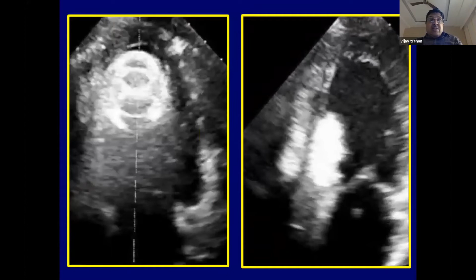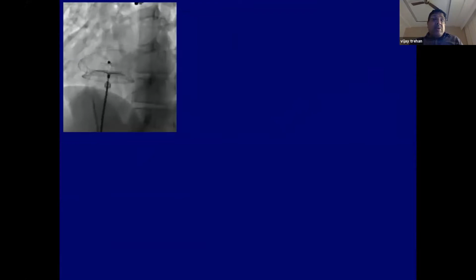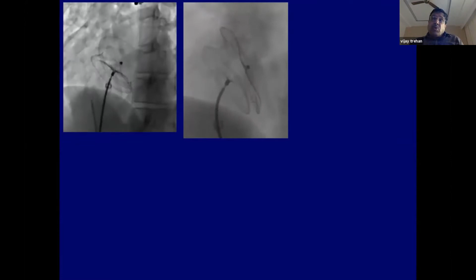So nobody will like things like this after you have delivered a device, but that can happen. Of course, nobody will release a device which is unstable like this, because all of us know that we have to check for the stability, and we check for the stability like this. We do a Minnesota in which we try pull and push. We should not be very aggressive, but often we do it. And even a device which has been tested to be very, very stable, like this case, did embolize.